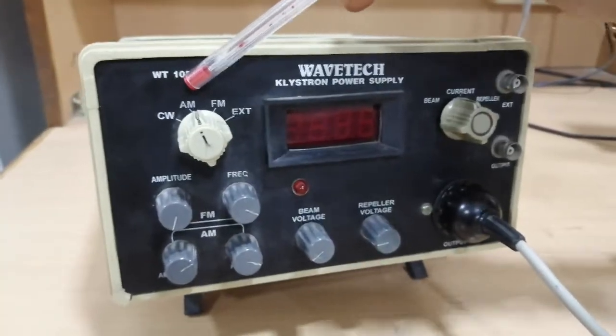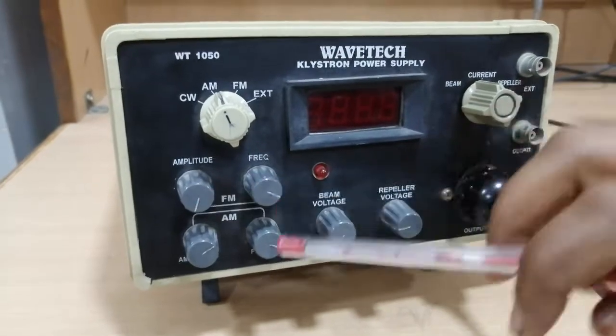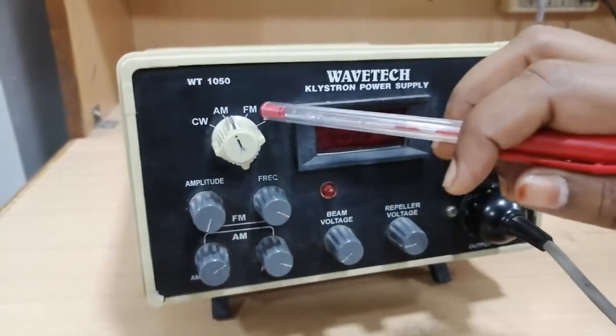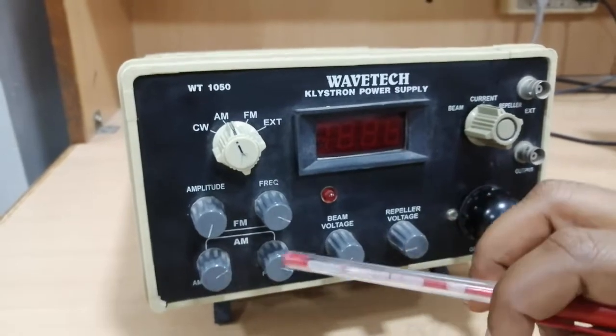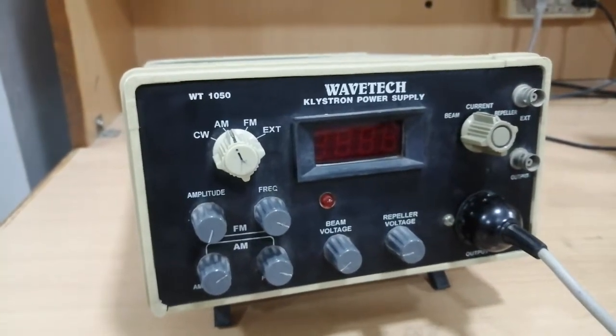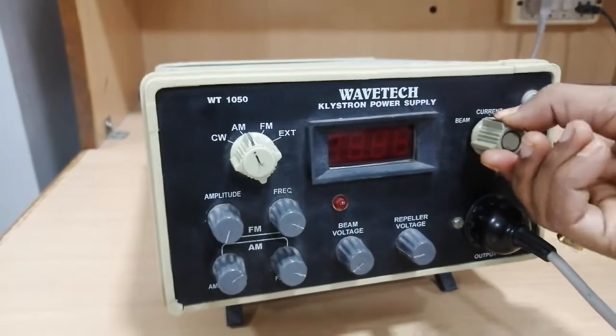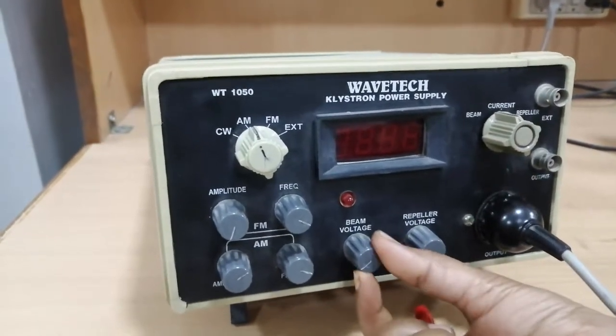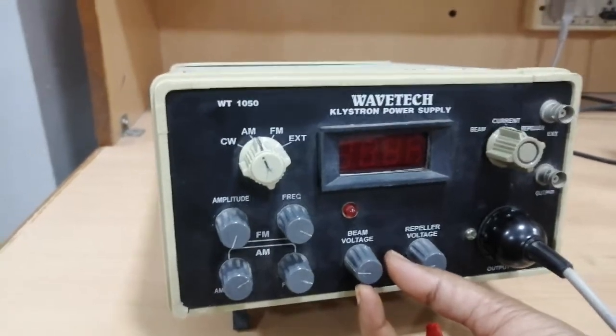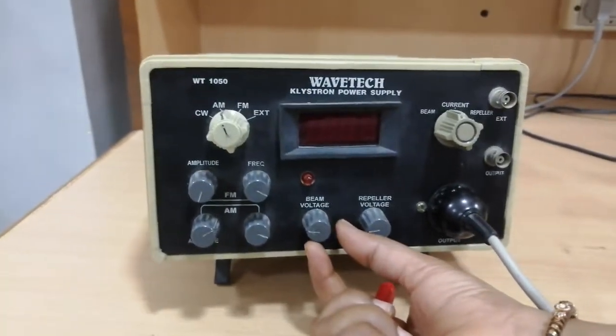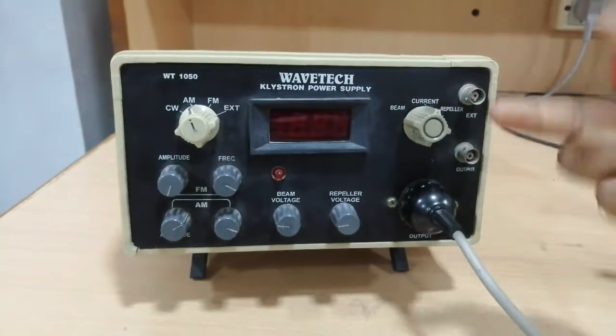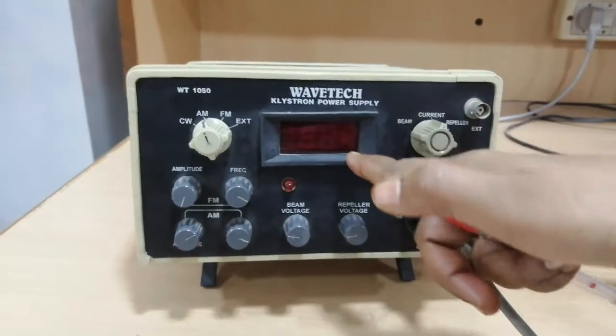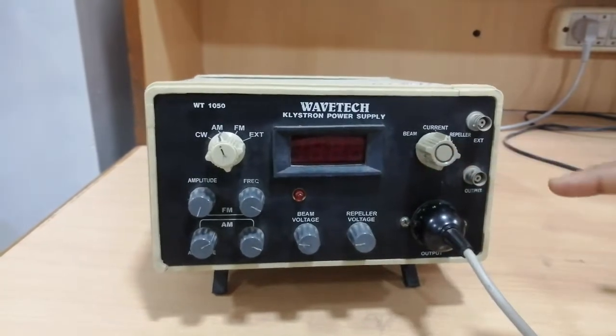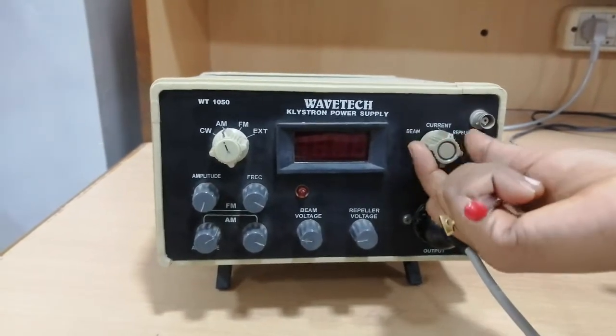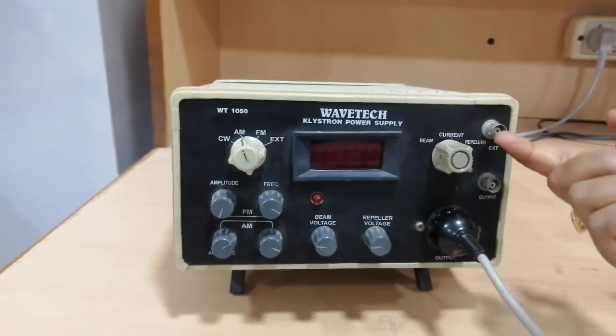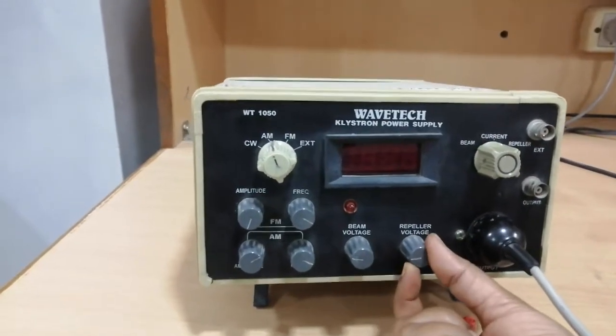See here we are having AM. For AM we'll be having two knobs, amplitude and frequency. Even for FM we can have two knobs, amplitude and frequency. In order to vary the beam voltage, we have to keep this knob at beam position and vary this knob. Generally this must be around 300 volts, or up to 300 volts you can say. And next we have to move this knob to current position. So directly we can see the current in this display, and that current will be around 20 milliamperes. And finally we'll have a repeller voltage. In order to vary the repeller voltage, this must be varied.